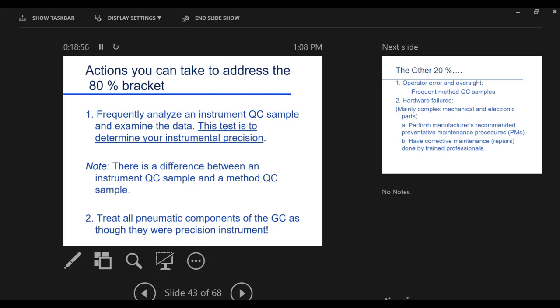That's step number one. There's a difference between an instrument quality control sample and a method. I'm taking a pure compound, reference compound. I'm putting it in solution. I want to see, do I get the same response out of my instrument. For a method, I would put some kind of an internal standard back into my sample. Go through all extraction, concentration, everything, all the handling, manipulation, and injecting it into the instrument. So this goes all the way back to the sample and checks, did you do the extraction the same way? Did you do the concentration right? Did you do every step of this processing? This one just looks at the instrument. This one looks at the entire method. And you've got to do both of them. If something fails, what fails? Did you fail somewhere in the extraction? Did the instrument fail? So again, for my students, they go through both of these and they go through them routinely.